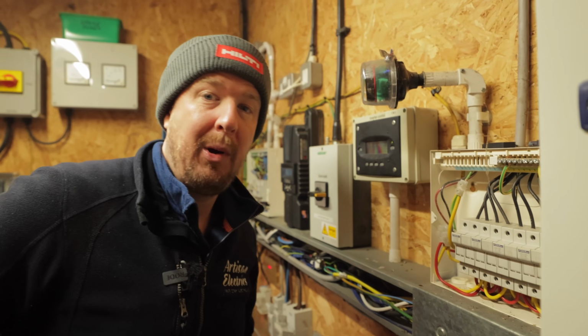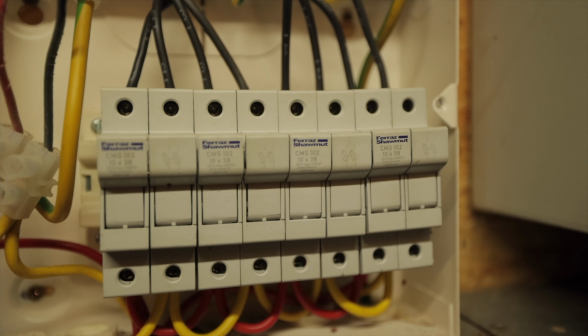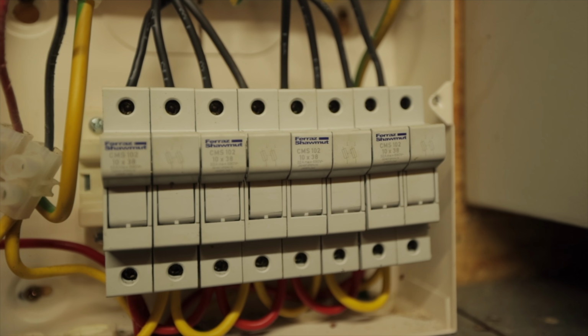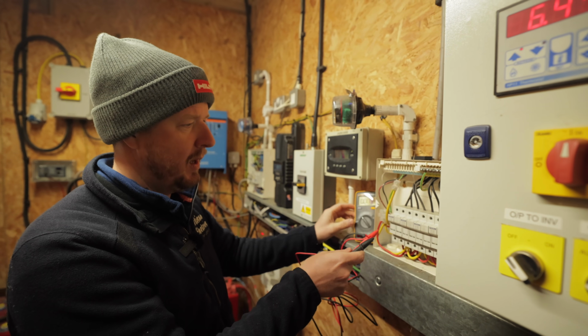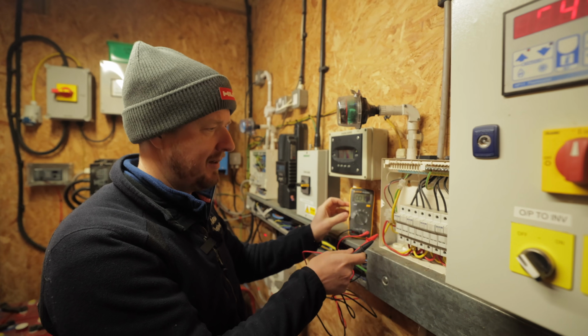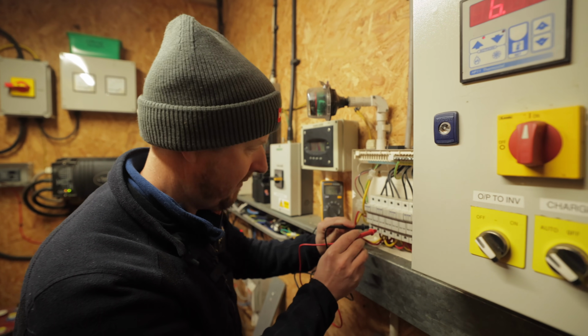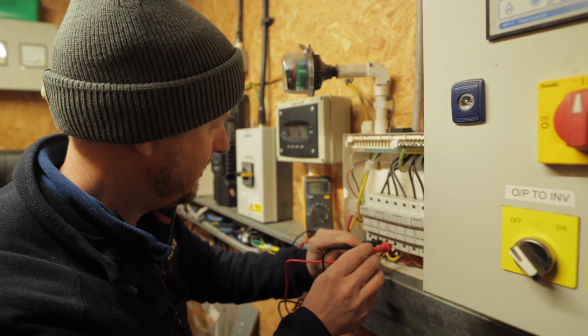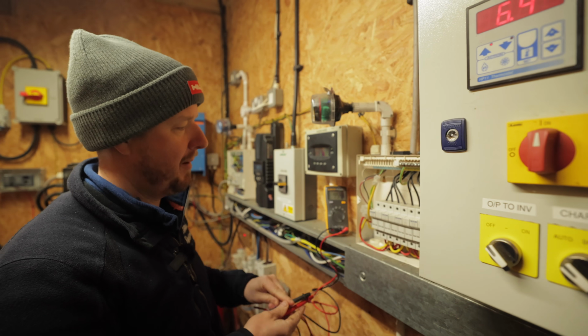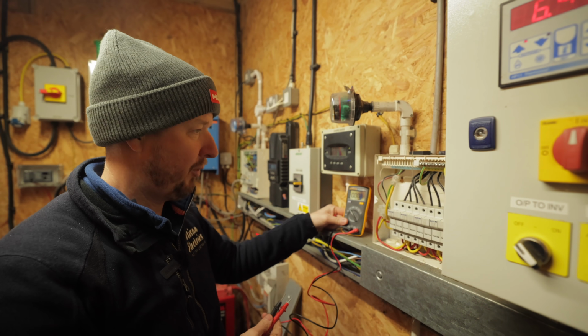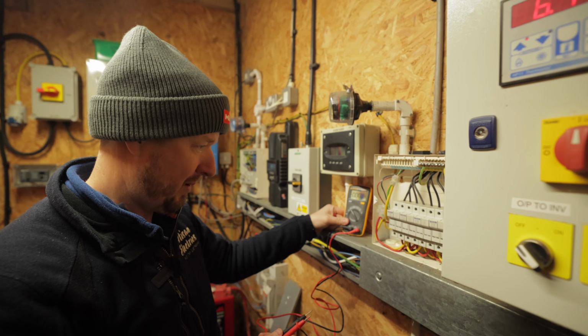Wow, the plot thickens. For 8 panels, there's a lot of string fuses. They're double pole units, so you're fusing the positive and the negative. So I can see here we've got 99 volts DC on that one, and 99 volts DC on that one. So they must be just under 50 volts per panel, so quite high voltage panels.